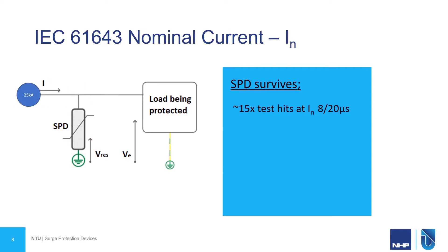IN is the nominal current rating of an SPD. There is a test procedure with this, but to summarize, it basically means that the SPD can be tested to this current 15 times and the SPD itself survives. Note that this uses an 8 over 20 microsecond waveform, so this is a Type 2 test.